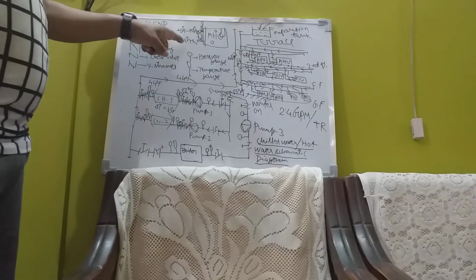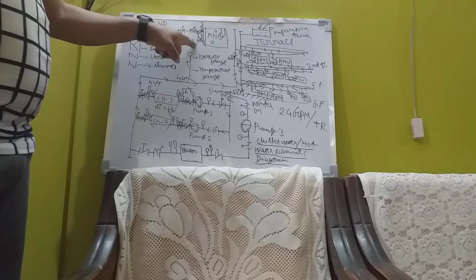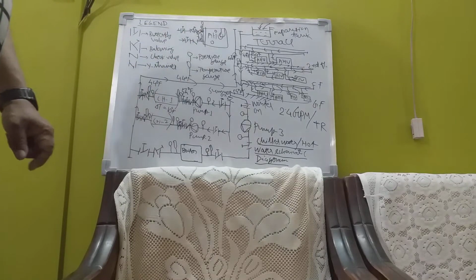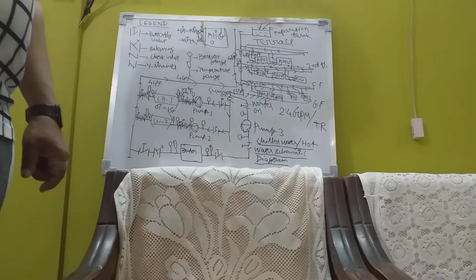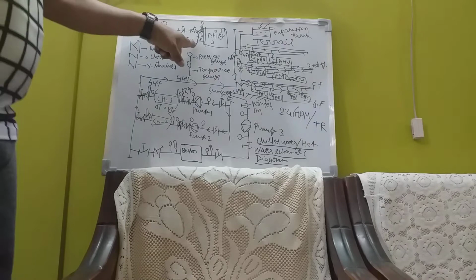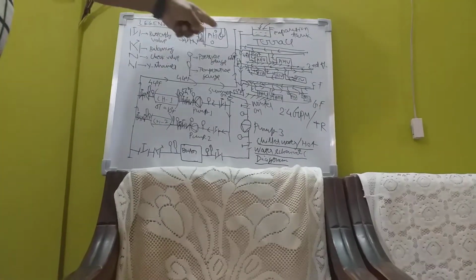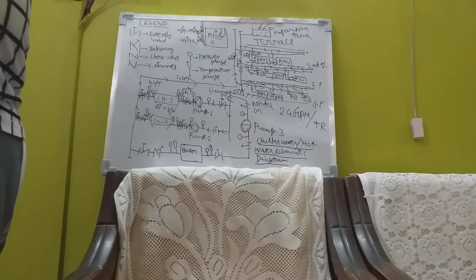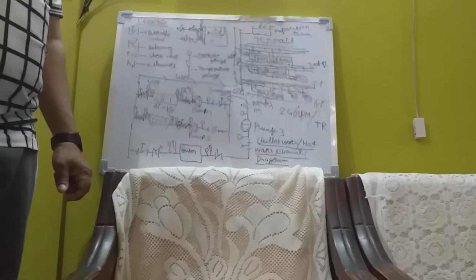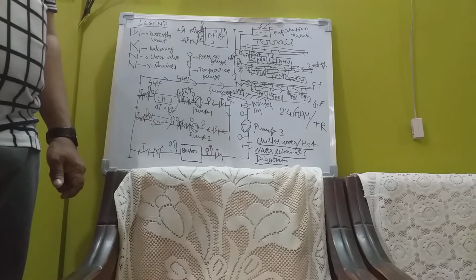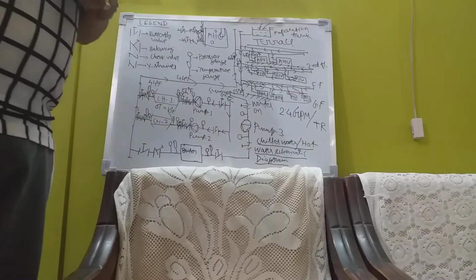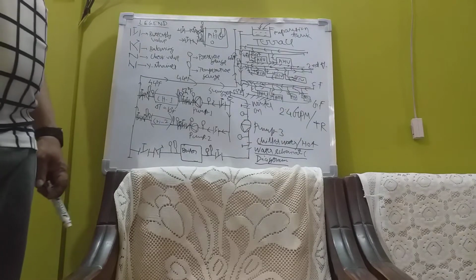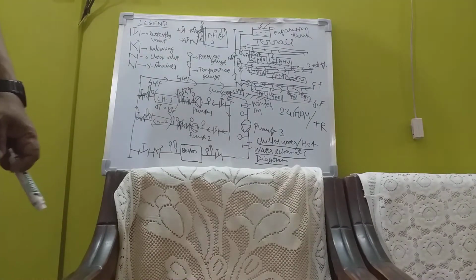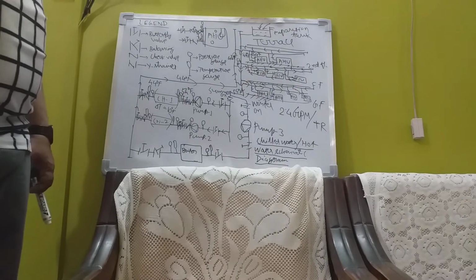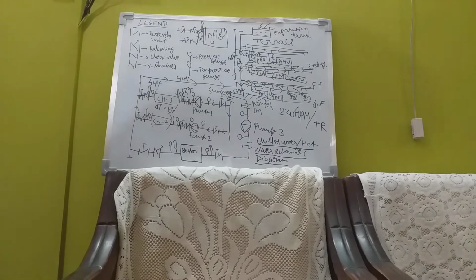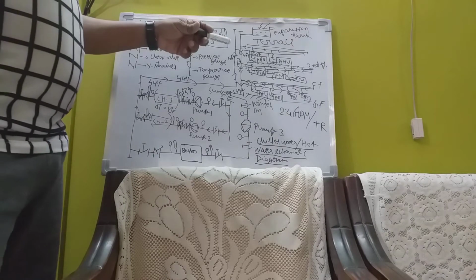Now, in case of this AHU, there is a butterfly valve, there is a Y-strainer. The Y-strainer is generally used to clean all the dirt particles or waste products in the system, because though it is a closed water system, there may be rusting in the pipe, there may be dust particles due to little bad quality of water, and these dust particles should not enter the cooling coil, because if dust particles go to the cooling coil, it produces fouling in the cooling coil, and as a result, the resistance to heat transfer increases. To decrease the resistance to heat transfer, we generally provide the Y-strainer.